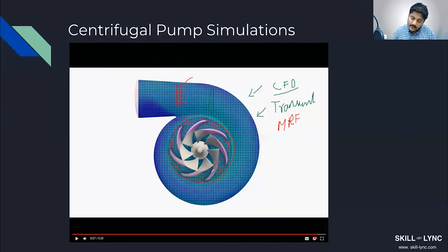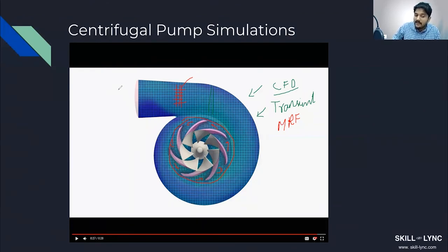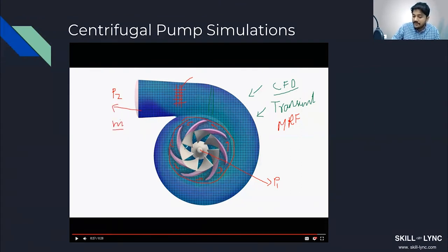If you ever simulate pumps using MRF, remember it's an approximate technique. It gives good answers for performance curves. What you do is vary the boundary conditions — the outlet pressure p2 (delivery pressure) and inlet pressure p1 at the eye of the impeller — and the computational code will simulate the mass flow rate. Repeating this for different delta P values gives you your performance curve, which is called virtual testing.